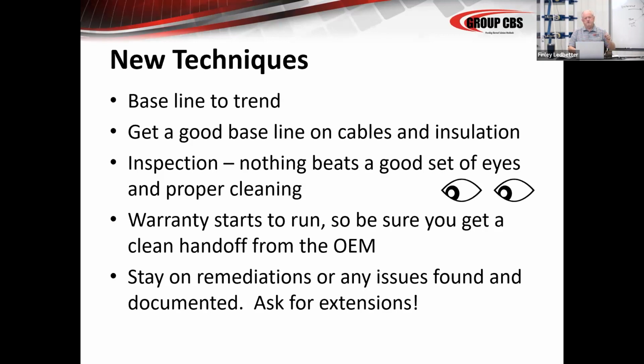All the jumpers are off, all the grounds are correct, everything's installed right, all the wiring looks right, you've done the pull test, you've inspected, you've run all the controls. Nothing beats a good visual inspection. So make sure part of the initial acceptance testing is someone that knows what they're doing, that knows this equipment, has looked at every inch of it, and it's been properly cleaned to start with.